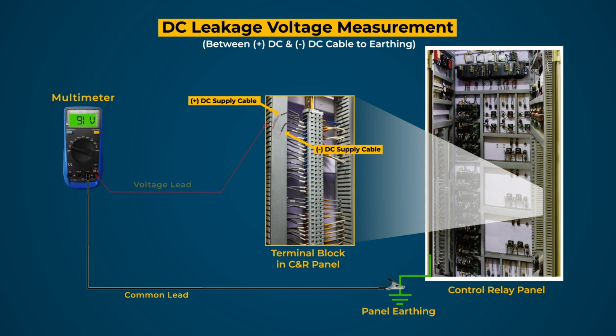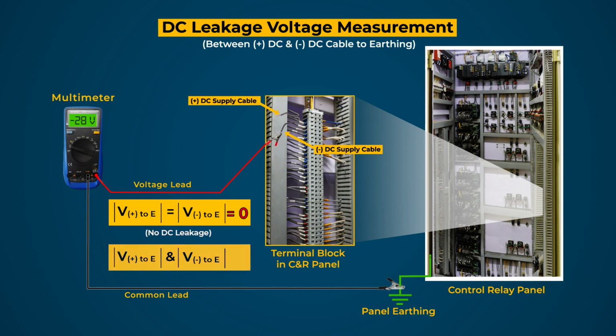Measure the voltage between negative DC supply and earthing by the same procedure and record the multimeter result of DC voltage magnitude, that is, voltage of positive DC supply to earthing and negative DC supply to earthing. Now, if both voltages in magnitude are 0, then there is no DC leakage. But if both voltages in magnitude show some value other than 0, then it means cable or leads of DC supply is damaged. So track the location of DC leakage and rectify the issue.